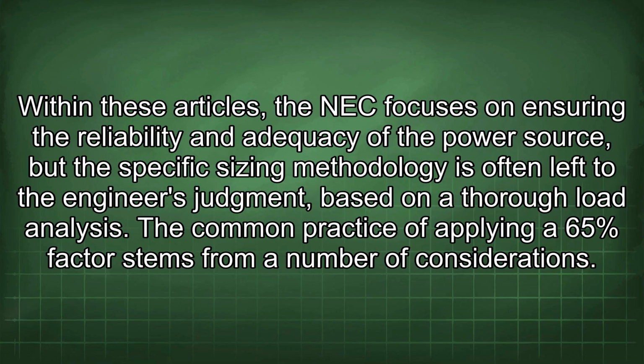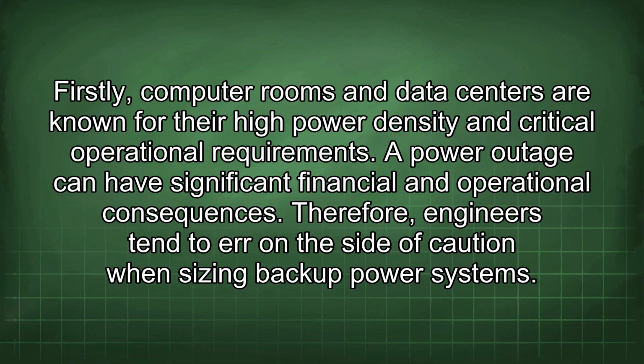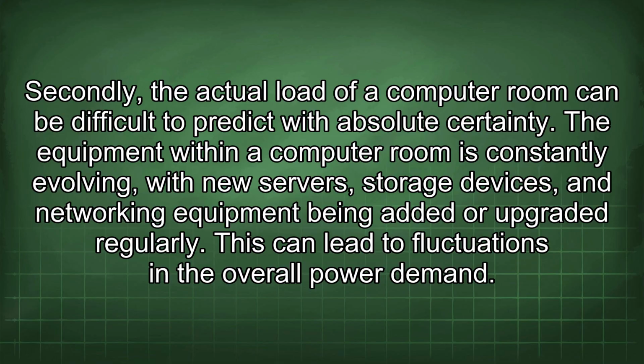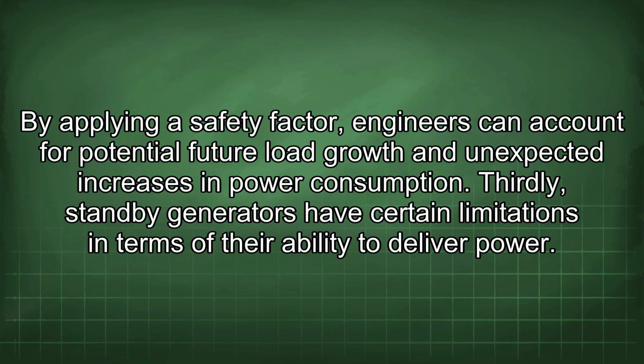The common practice of applying a 65% factor stems from a number of considerations. Firstly, computer rooms and data centers are known for their high power density and critical operational requirements. A power outage can have significant financial and operational consequences. Therefore, engineers tend to err on the side of caution when sizing backup power systems. Secondly, the actual load of a computer room can be difficult to predict with absolute certainty. The equipment within a computer room is constantly evolving, with new servers, storage devices, and networking equipment being added or upgraded regularly. This can lead to fluctuations in the overall power demand. By applying a safety factor, engineers can account for potential future load growth and unexpected increases in power consumption.